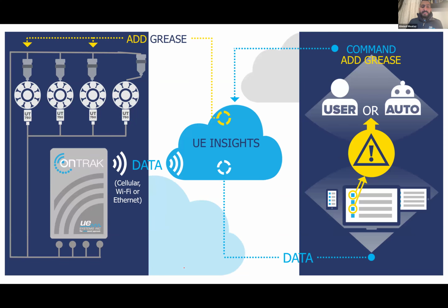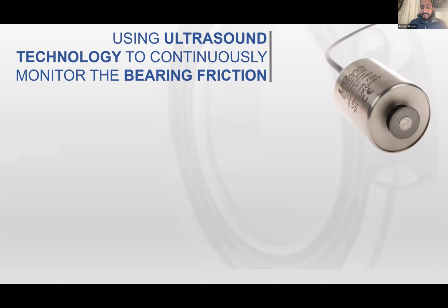Basically, the OnTrak Smart Loop solution consists of remote sensors mounted on the bearings, and remote cartridges with a specific amount of grease. So I'm making sure that I'm adding the right lubricant volume without any contamination, as per the bearing demand, not as per a timesheet or a time schedule, just following the change in the decibel value.